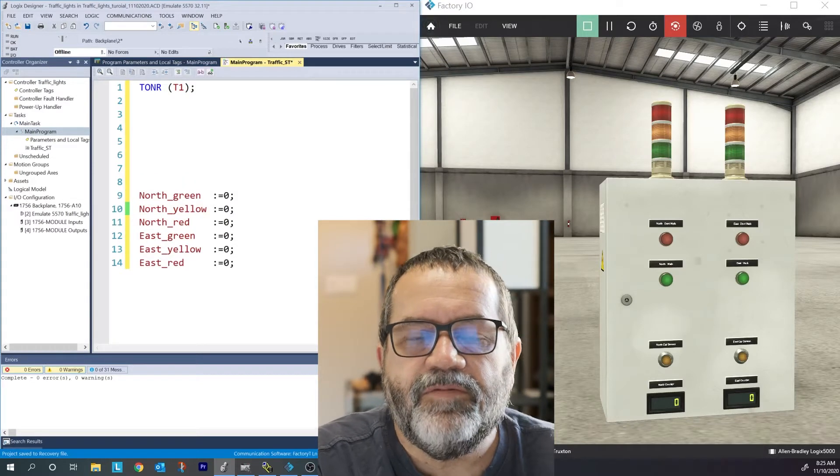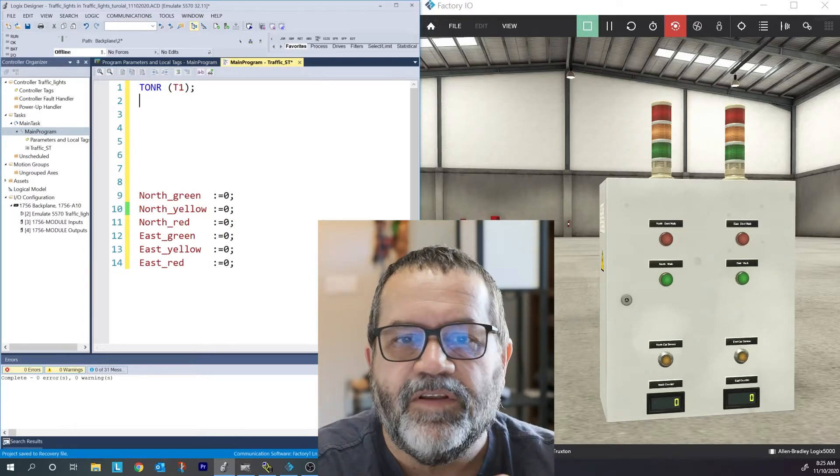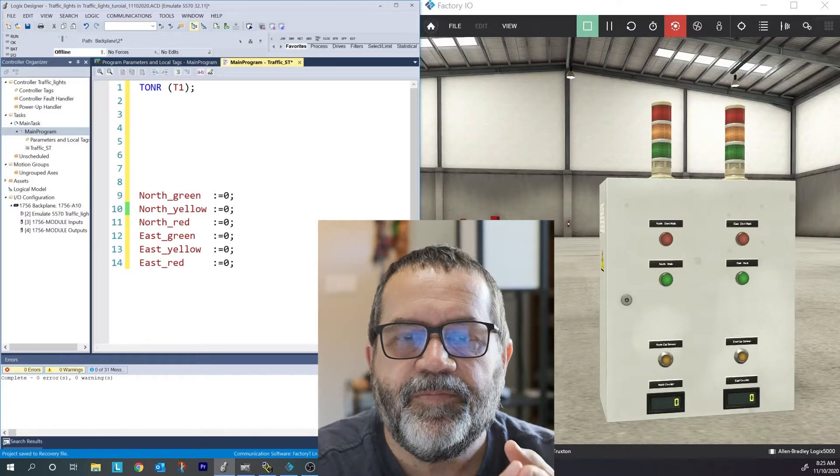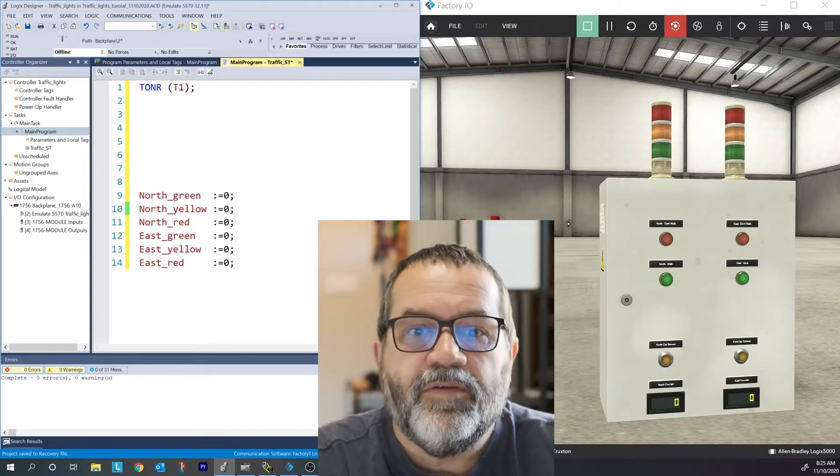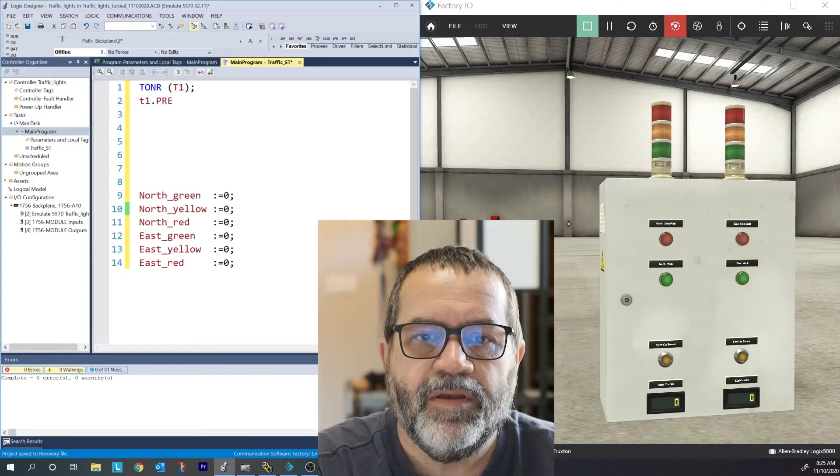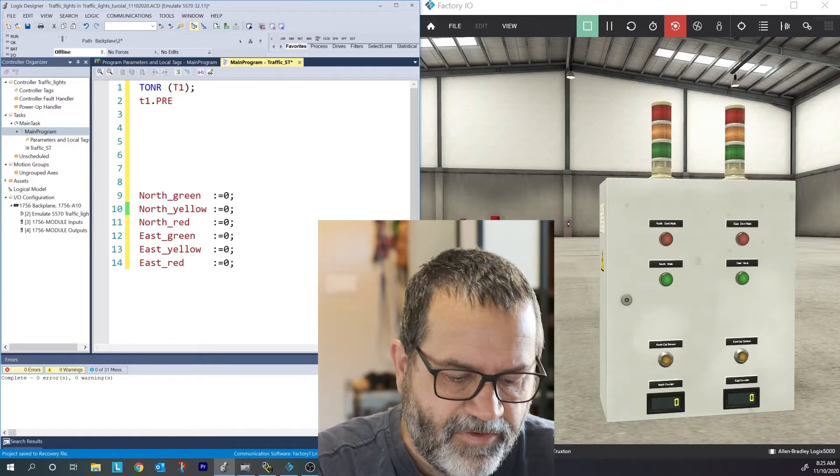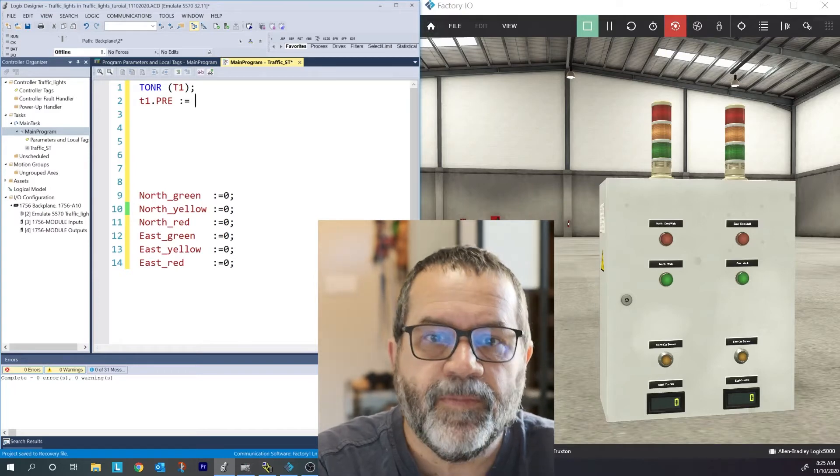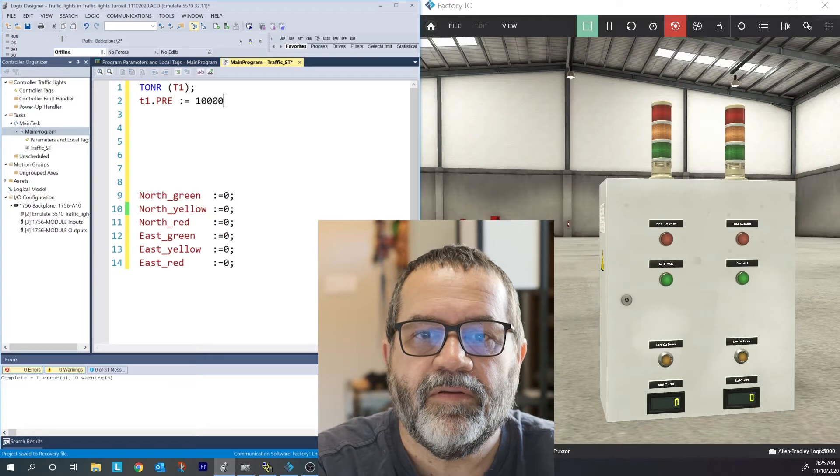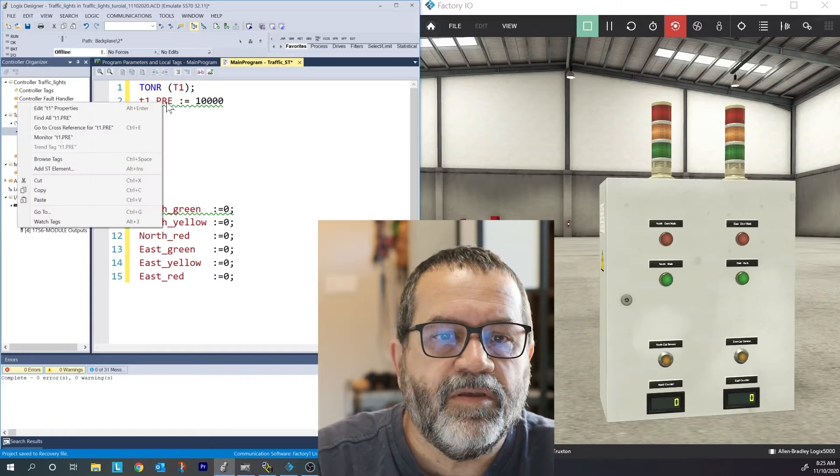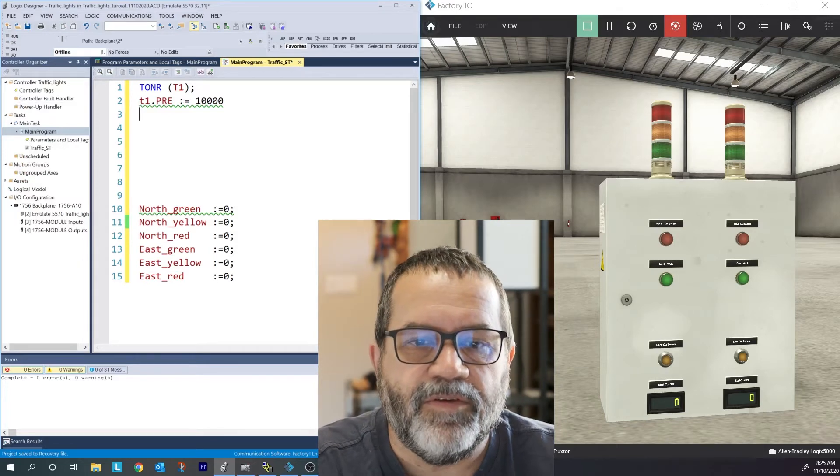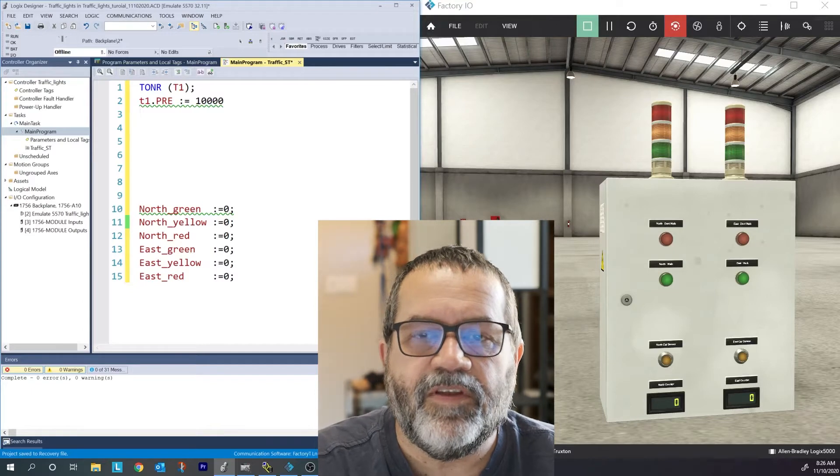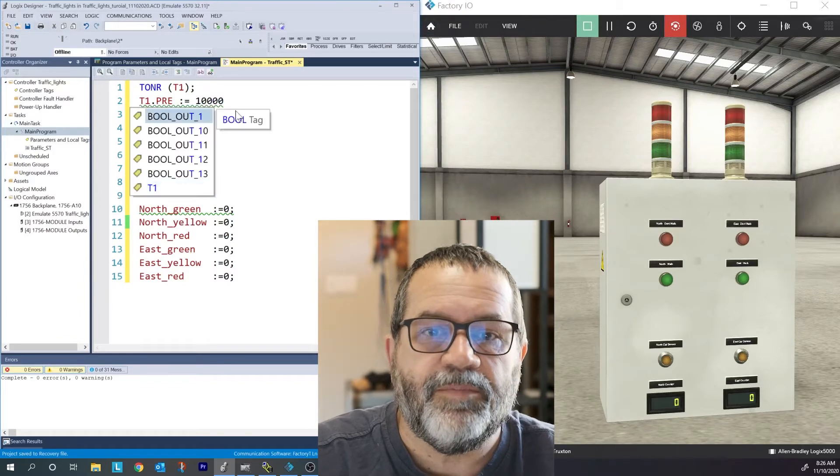Next thing I want to do is I want to set up my timer to run. So I want three things I need to put in. I need my preset, I need to lock it on, and then I need to have it reset as soon as it finishes so that it starts over again. First thing I need is my T1.PRE and I'll set that to 10 seconds. Structured text doesn't really care about capitals. You can use small letters or capitals. Sometimes it's easier to stay organized if you use capitals, but it's kind of a personal choice.